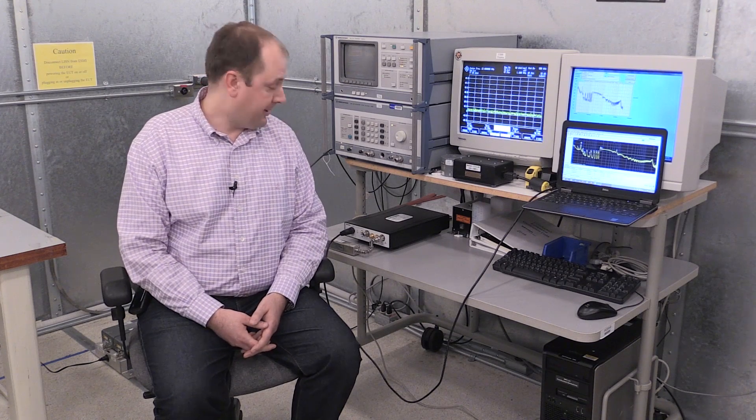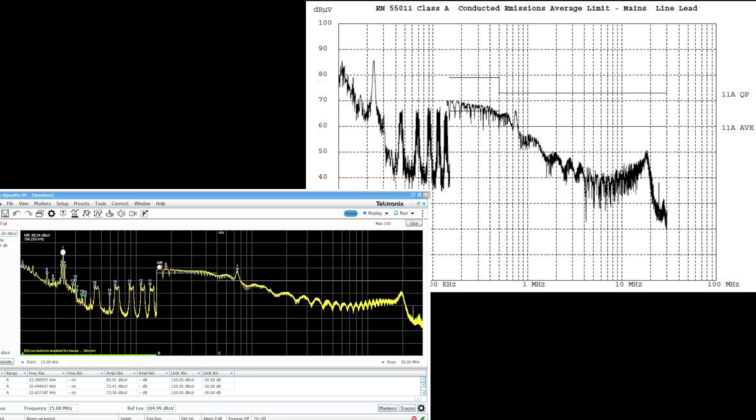So here's the side-by-side screenshots comparing the conducted emissions test with the results from the RSA on the lower left compared with the full compliant receiver on the upper right. You can see here again the traces correlate very nicely. In both cases I'm showing a CISPR peak detected trace and then I can actually see some failures in this particular case where I've exceeded the limit lines in some of the areas.